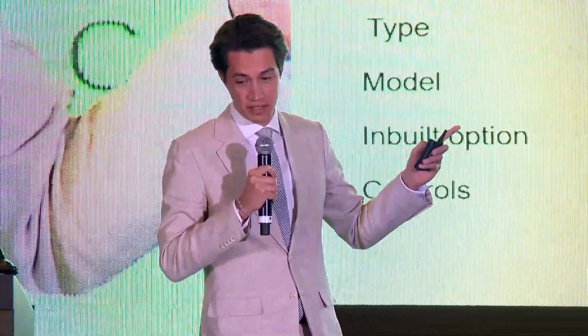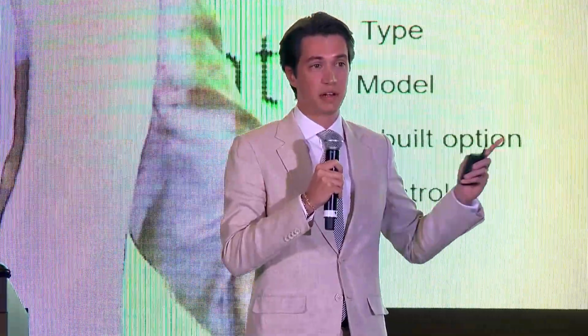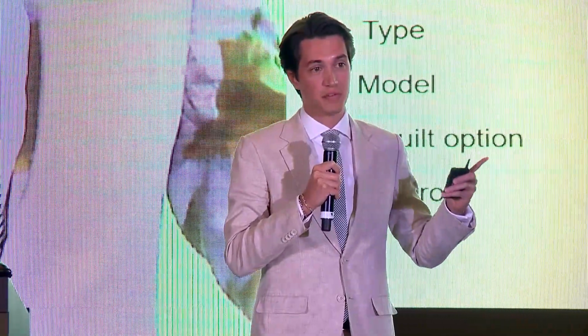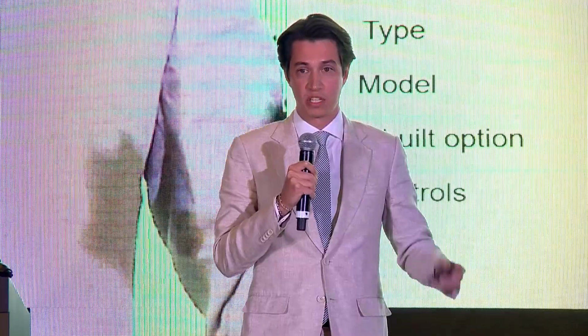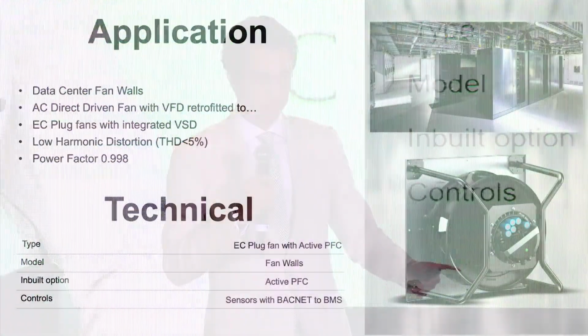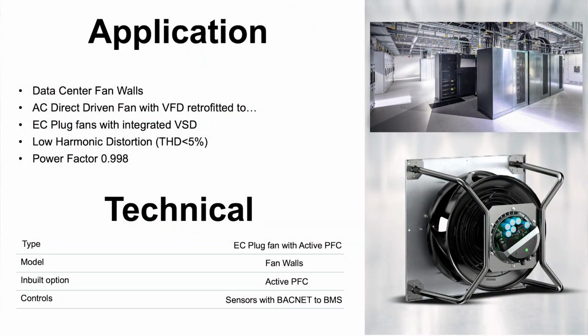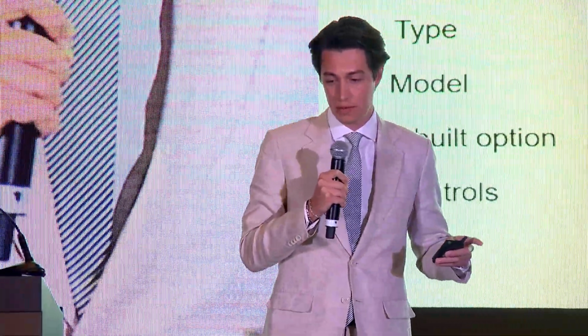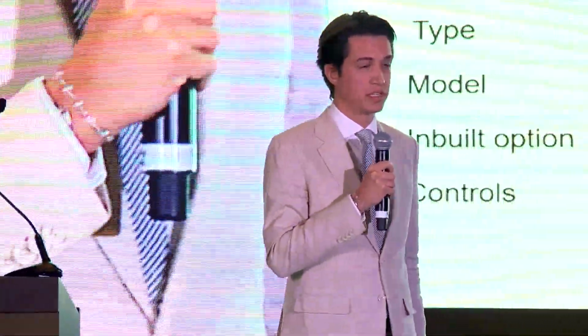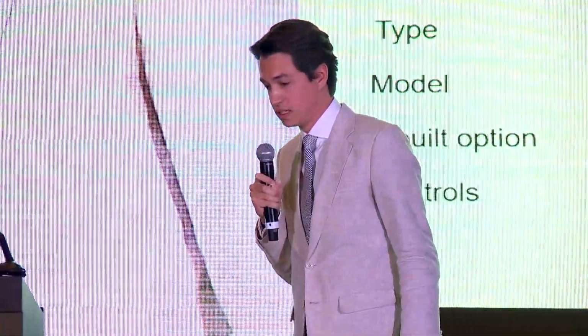In this case, EC plug fans with integrated active power factor correction. What does that mean? We have a THDI level, a total harmonic distortion level below 5%, which gives you a power factor of 0.998, almost close to 1. Still not perfect, but still good technology.